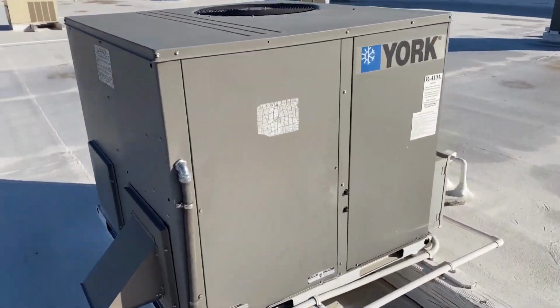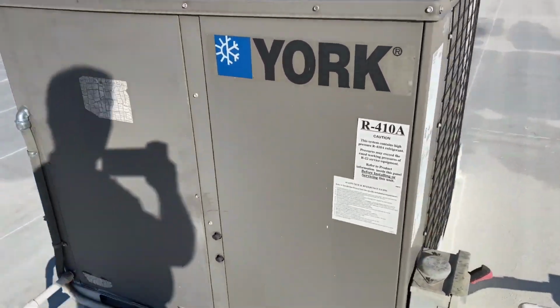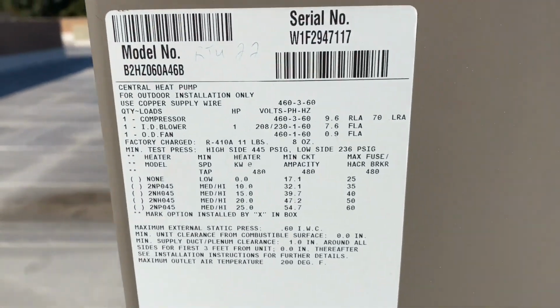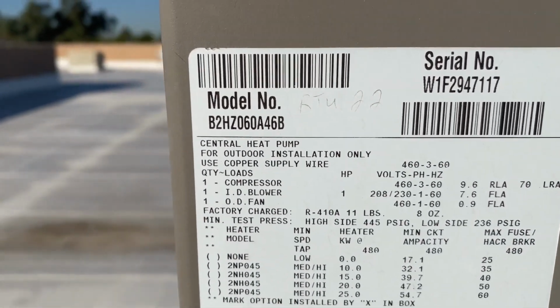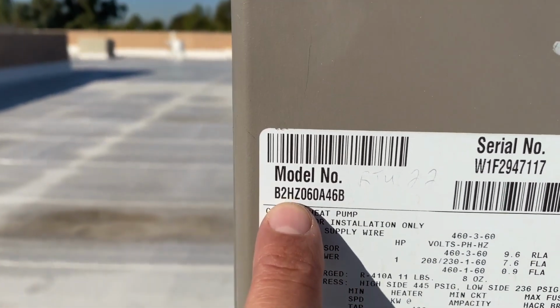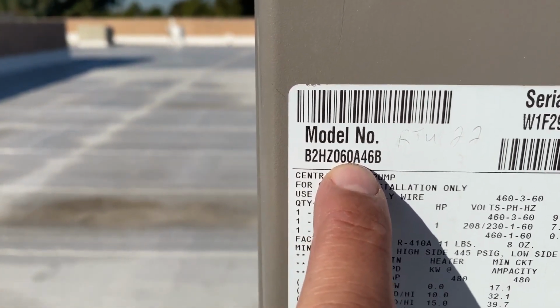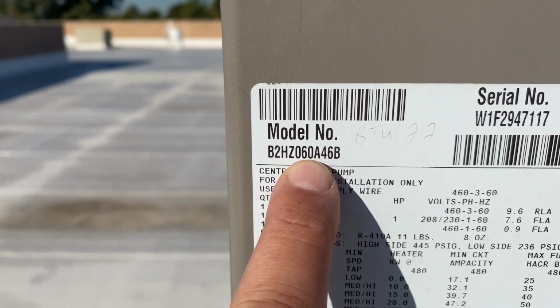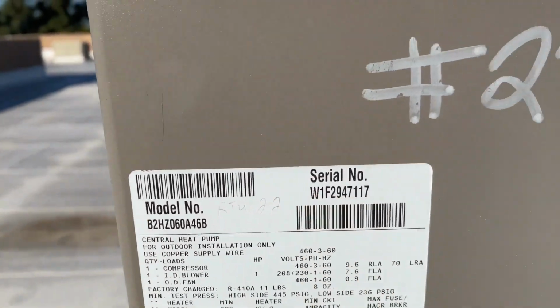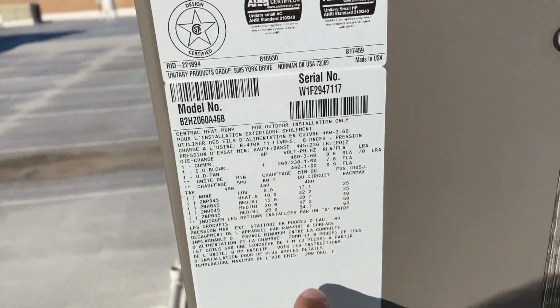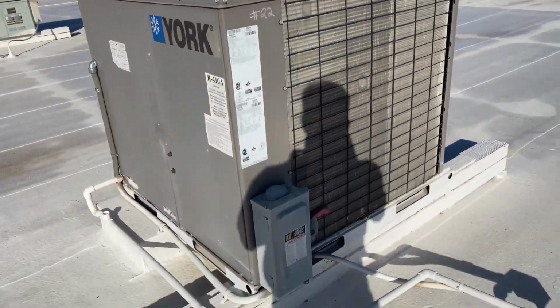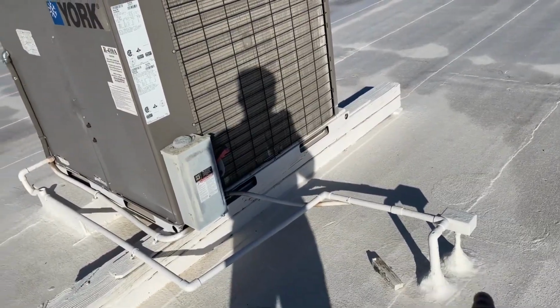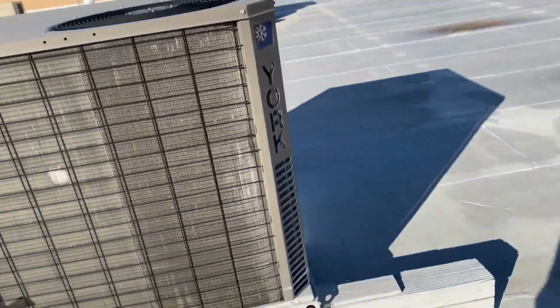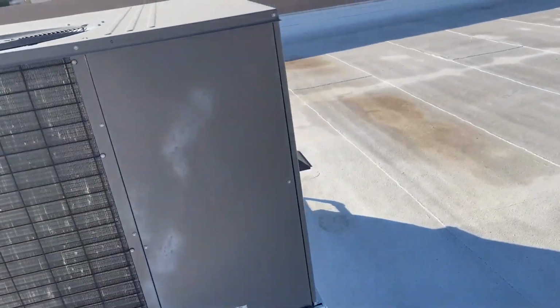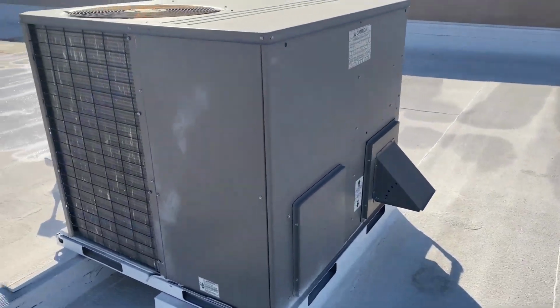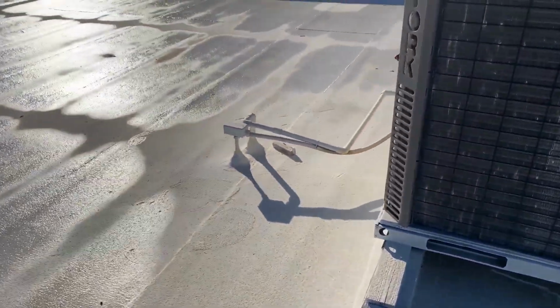Okay, so we are on the roof now and I'll show you how to look at these units. This is what we do. So we look at the model number, which is this number here, and this 60 is going to be a 5-ton. If it's 48, it's a 4-ton. Here's the serial number. We usually take a picture of all these specs. This is a York. You can see the power here. There's a disconnect. And there's a fresh air intake. So those are the requirements, that you have a power outlet.